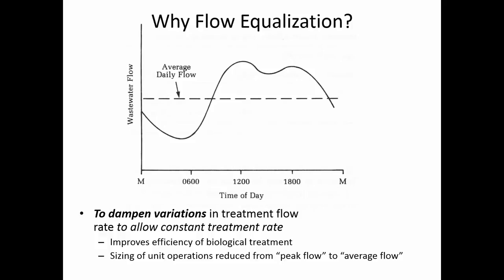When we go through the procedure today, we're going to add a safety factor to make the flow equalization basin bigger than the figure shows. You need to definitely design the basin for what you consider your maximum condition. When you first build a sewer treatment plant, there are relatively few people using it because you build a treatment plant maybe to serve a 30-year design life. When you size each component, you need to think how many people are going to be using this facility at the end when the city has grown. It's important to size them with future demands in mind.